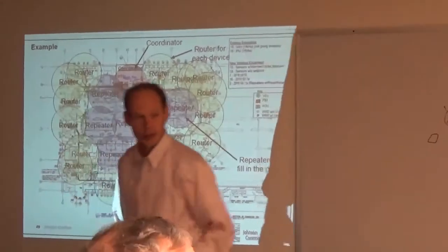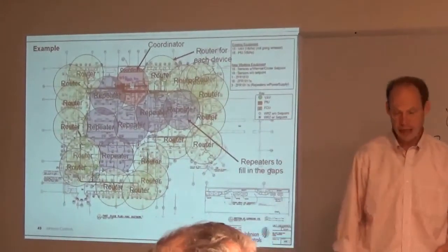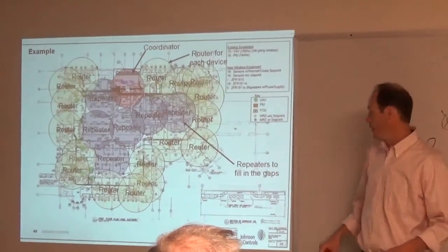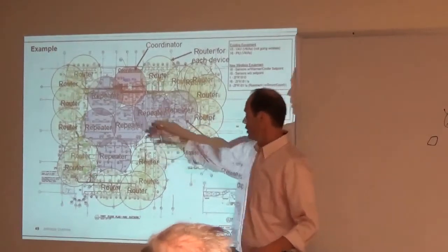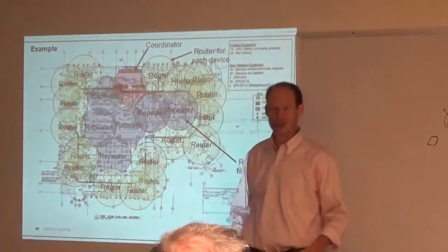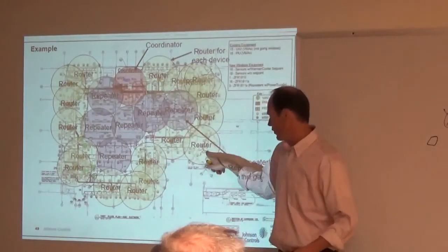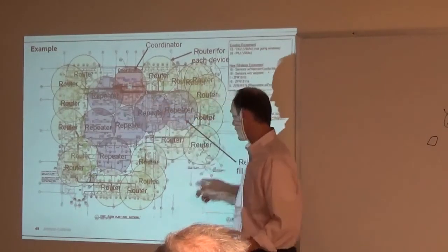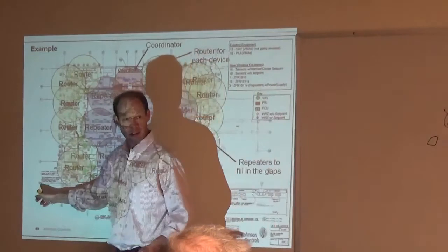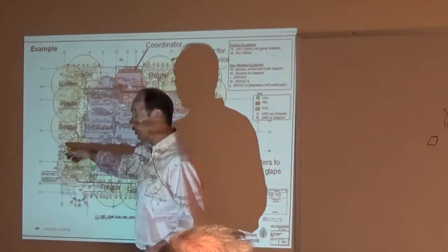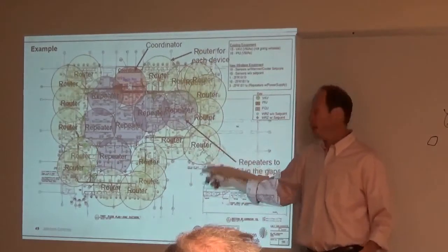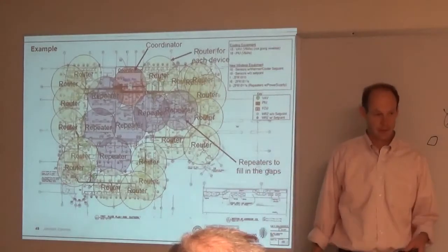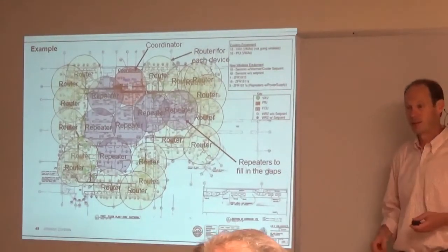It's a communication between the sensor and the controller, this guy right here; throw the flag in there. The flags create the mesh, and the coordinator creates the mesh. The sensors just ride on it. Maybe the sensor for this guy is mounted on the wall right here, and let's say this is personal area network number 7. I can take the sensor off the wall, go all the way over here and mount it. It'll hop up here and go, I need to go back to this controller over here, and communicate my value to this guy. So the sensors don't form the mesh.